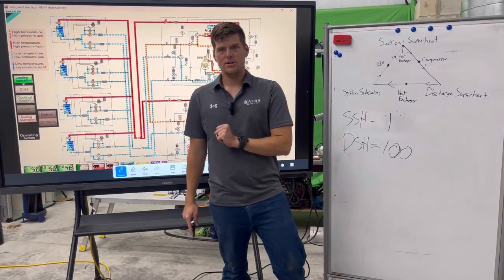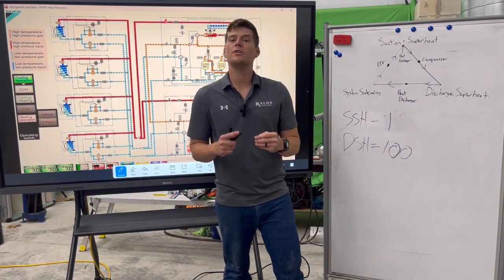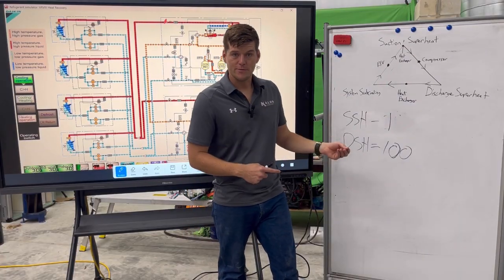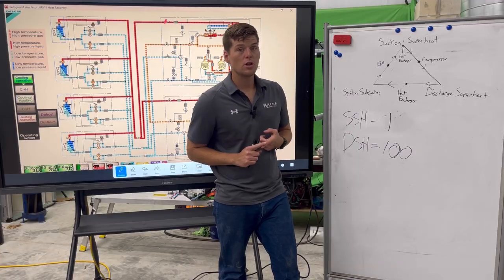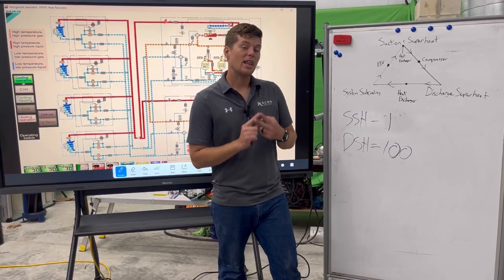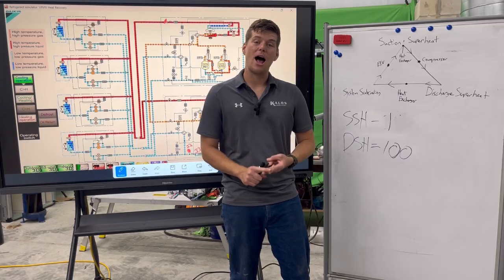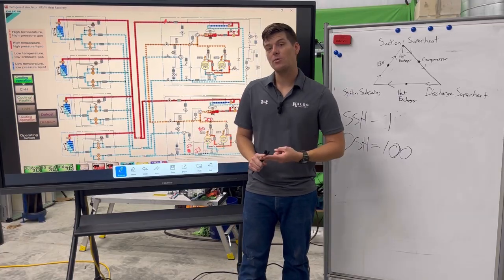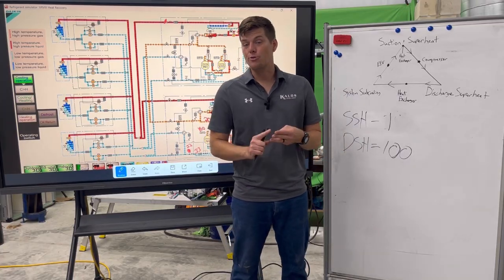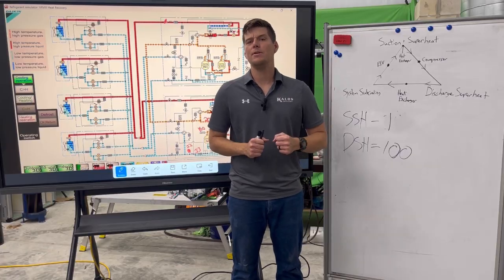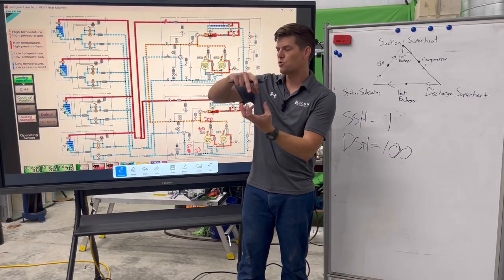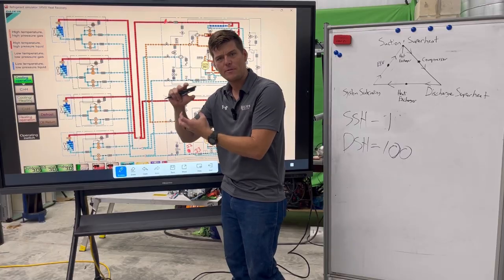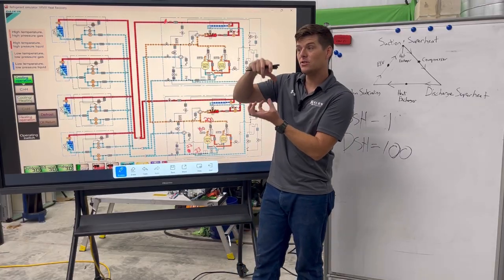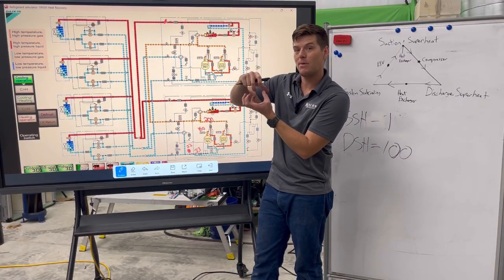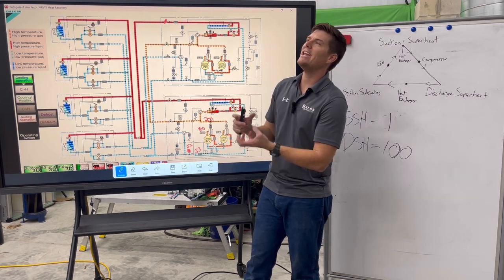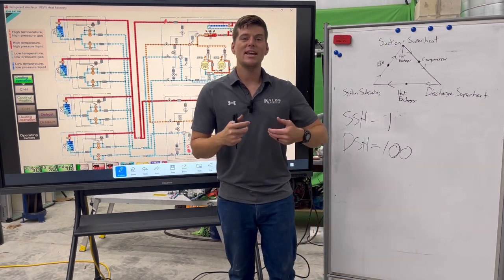Why would it be at 100 discharge superheat? Well, so here's the thing about compressors that chew on liquid for extended periods of time. One, they lose a large amount of oil, but then two, the lack of oil within the compressor wears out the bearings at both the top of the compressor and the bottom of the compressor in 3 different key places. So what happens when we lose that oil and you get 2 scroll plates that are grinding away on top of each other? Well, one, you lose the oil that seals the compression process in between, so you get some leak by, but two, you get an insane amount of heat. You get an insane amount of friction.